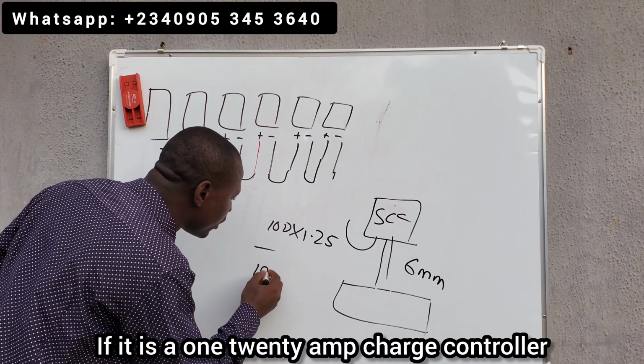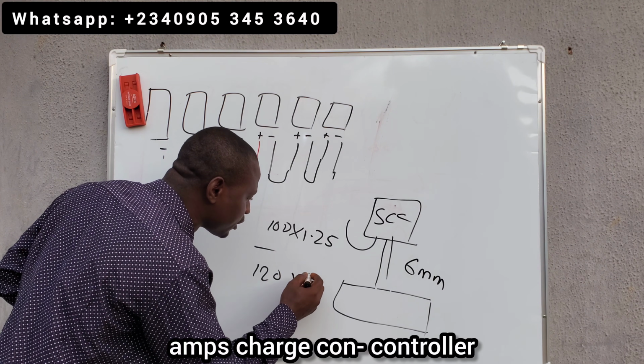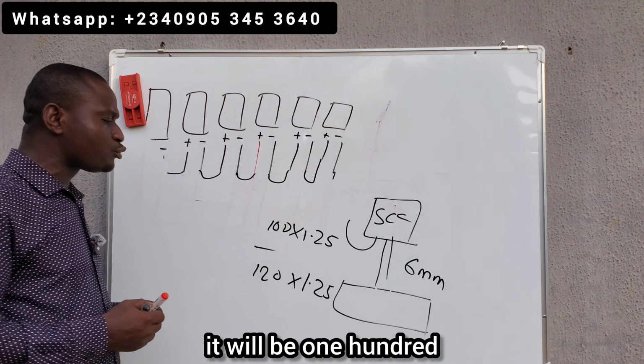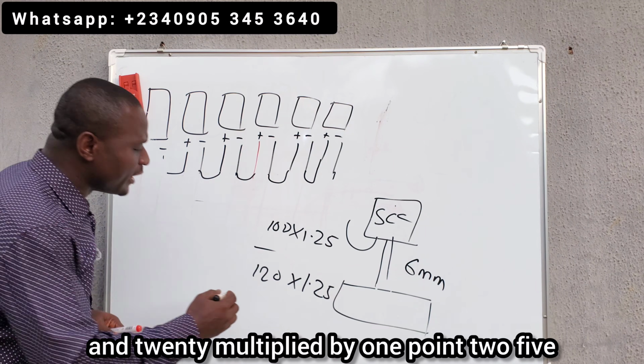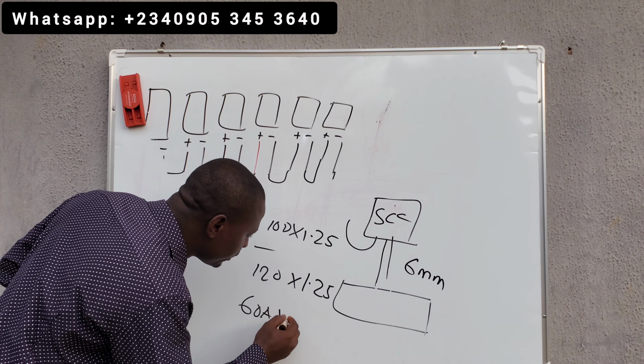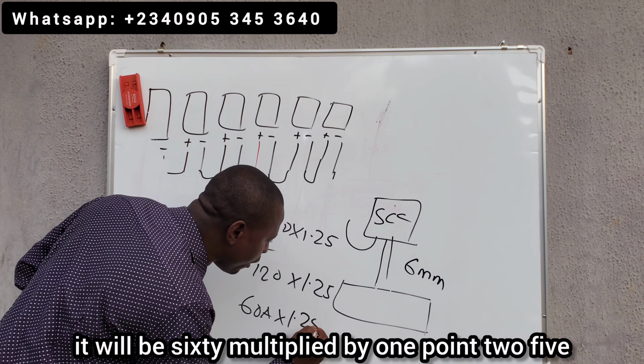If it is a 120 amp charge controller, it will be 120 multiplied by 1.25. If it is 60 amps, it will be 60 multiplied by 1.25.